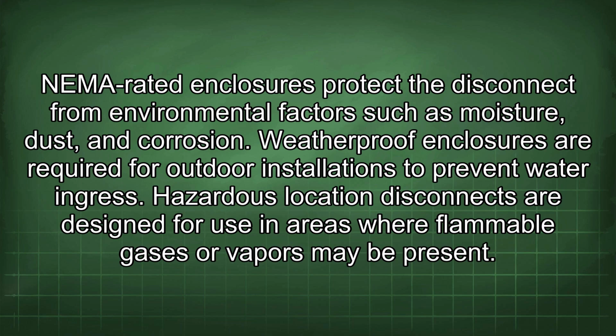NEMA-rated enclosures protect the disconnect from environmental factors such as moisture, dust, and corrosion. Weatherproof enclosures are required for outdoor installations to prevent water ingress. Hazardous location disconnects are designed for use in areas where flammable gases or vapors may be present.